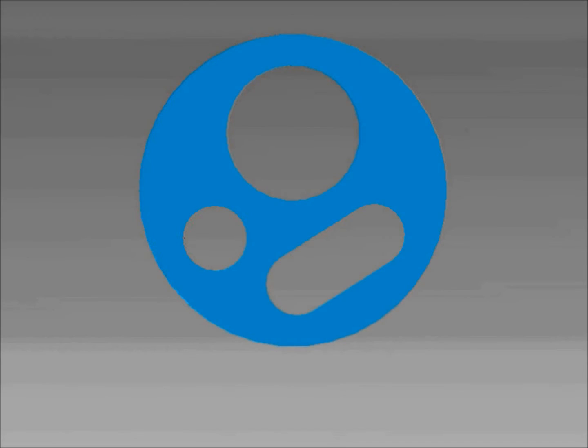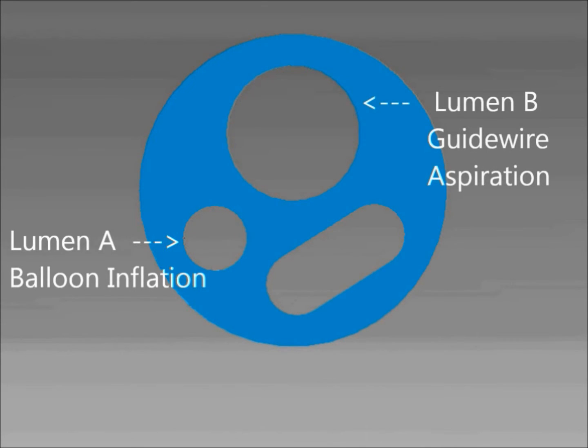The catheter extrusion uses three lumens, starting with lumen A, which is used to inflate the balloon, lumen B, a multi-functional lumen used for both guide wire insertion and aspiration, and finally lumen C, used for infusion of drug.